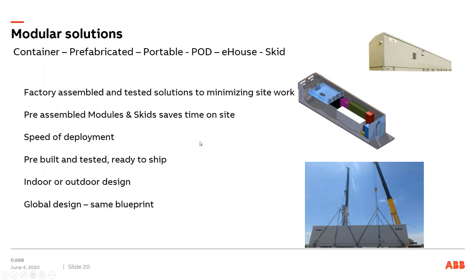One last thing I'll mention on this, what we are seeing also is that some customers are moving to what they call a modular skid-based solution. And the skid is basically just a big steel frame. So instead of building a building and then installing your UPSs and your switchboard or switchgear and distribution in there, they build the building. And then, especially for colos, they install the UPSs they need with the space that's rented from day one. And then instead of having to install individual UPSs and switchgear and all that good stuff every time they have to expand and add more power, they install a skid, which will include a UPS, typically the UPS and the power distribution, and if required, also a static transfer switch. All pre-assembled at a factory, pre-wired, and tested. So it's a fast way to add power.